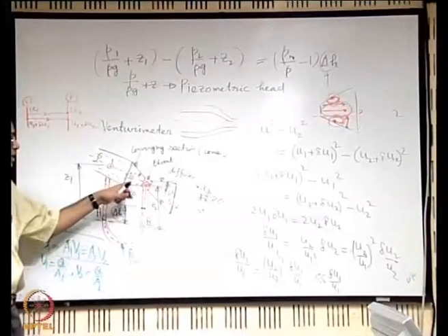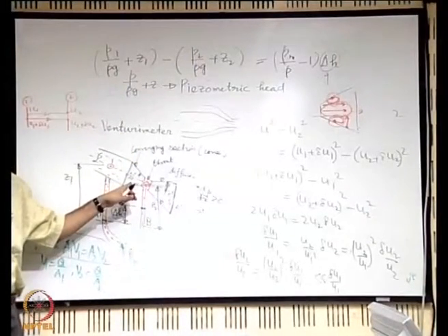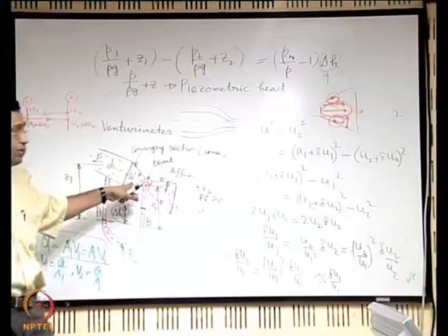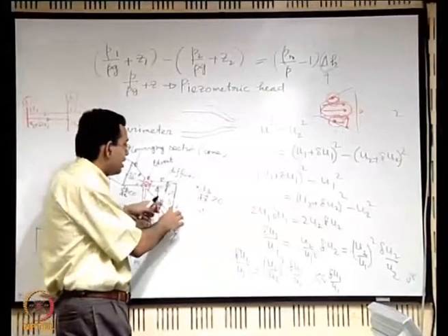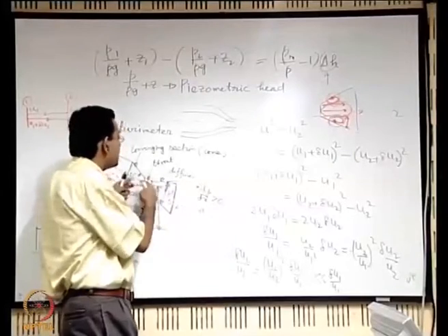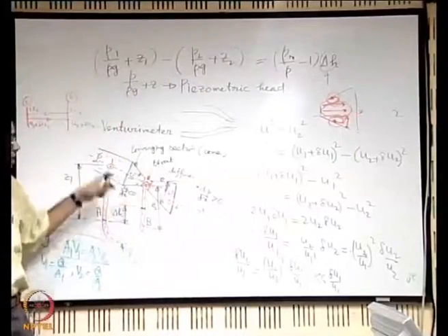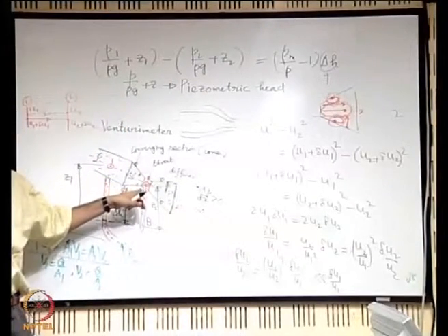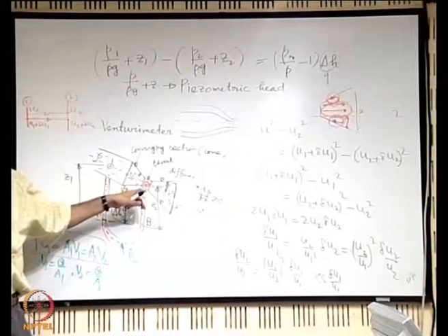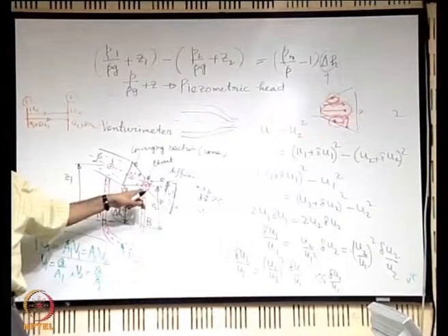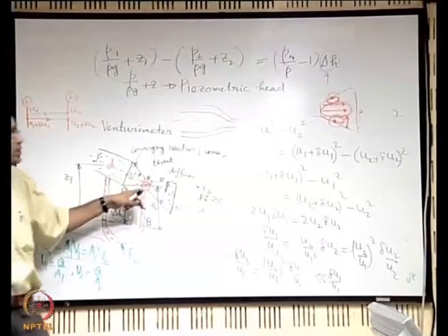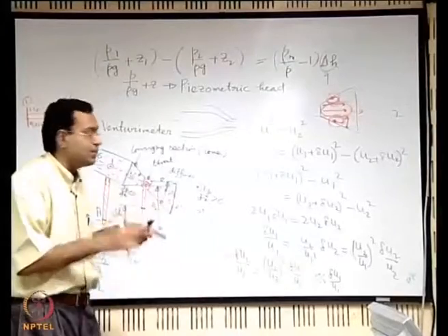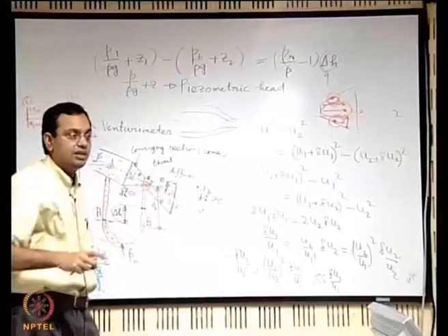much less than the angle of the converging section. So this is something we have to understand very carefully, why in the practical design the diffuser angle is much less than the converging section angle. When you have the converging section, you do not have such a case of flow separation. So only the frictional resistance, because of the length, is the important resistance, because flow separation will be there when the flow is decelerated, but in the converging section the flow is accelerated.